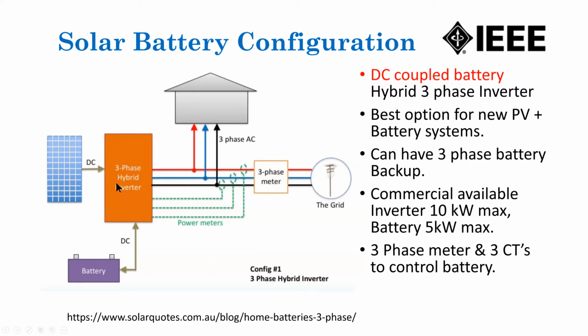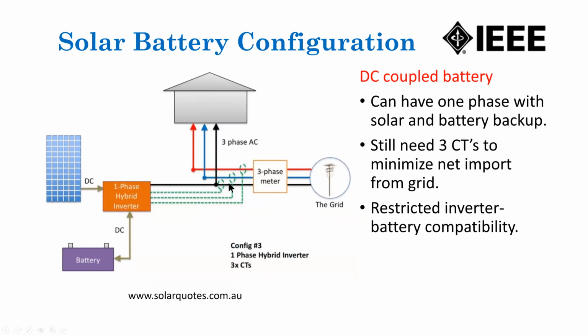So for some of the time, your solar panel will provide power, and it comes straight back into your house, and the net outflow is nothing. You can have commercial inverters available, typically up to 10 kilowatt maximum, and a battery is typically 5 kilowatt maximum. And you need a 3-phase meter and 3 current transformers to control the battery, even if it's a single-phase battery. You can have a single-phase inverter, so that you put power out on single phase, and then you've got your solar panel with your battery and single phase hybrid inverter. Depending on your system, you can have that black phase as a battery backup, so that if the power fails, the power gets turned off here, but your hybrid inverter can still produce power.